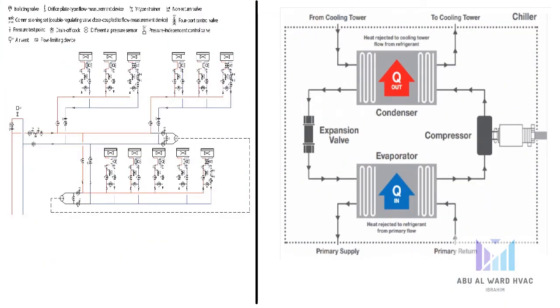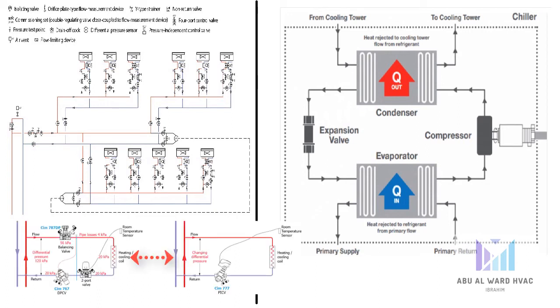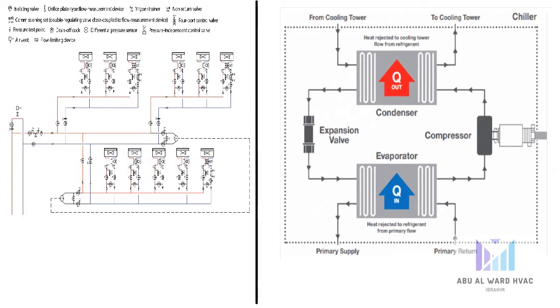Benefits: the PICV ensures balancing of the flow and eliminates the use of both static balancing valves and differential pressure control valves. Simple installation, as only the PICV is required with no need for additional pressure or flow balancing valves. Low total pressure loss in the system due to simple design. The flow can be set directly on the PICV without the need of a manometer or commissioning unit. The differential pressure only needs to be checked at the PICV to set the required flow.